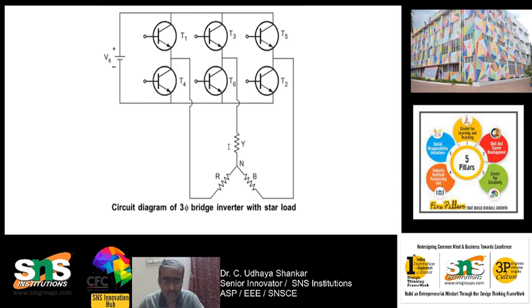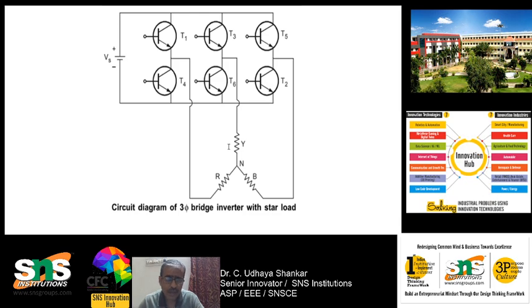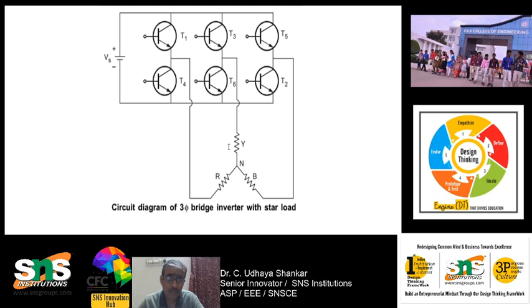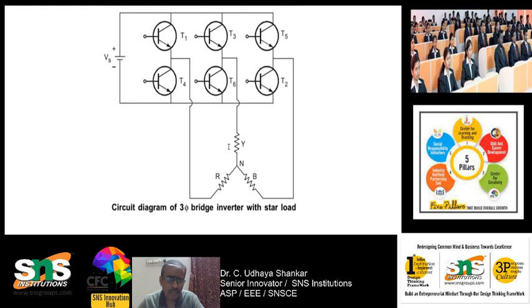Above one kilowatt or 1.5 kilowatts, normally a three-phase inverter is preferred instead of a single-phase inverter, because with a single-phase inverter the torque ripples become very high for high-power applications and the quality of output is reduced. The three-phase inverter uses six transistors.